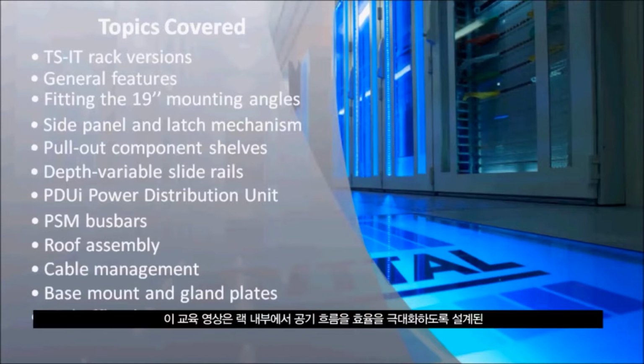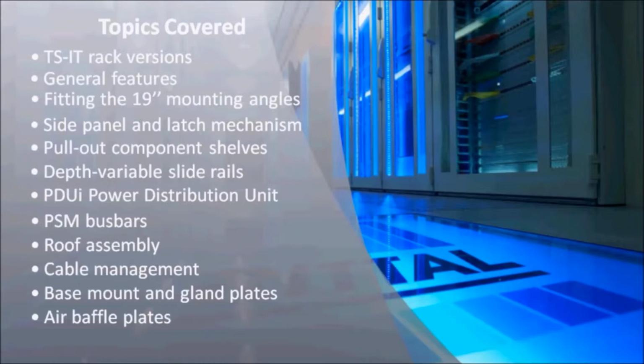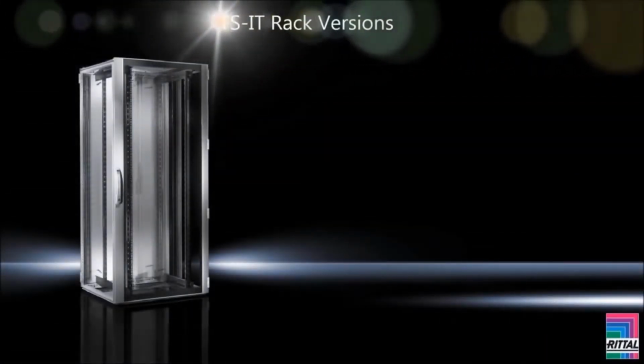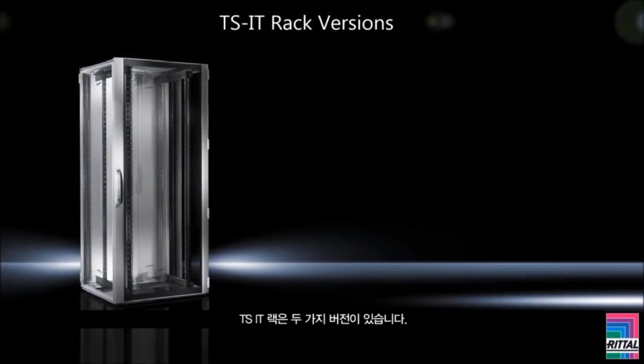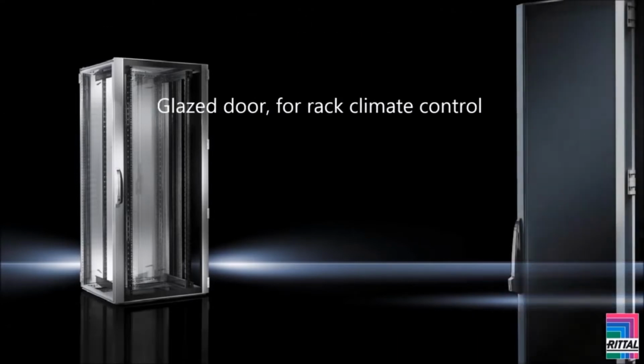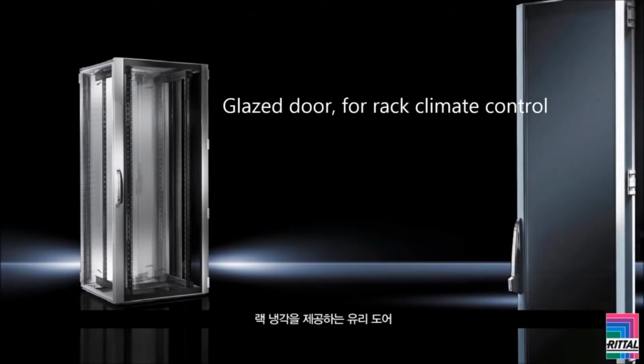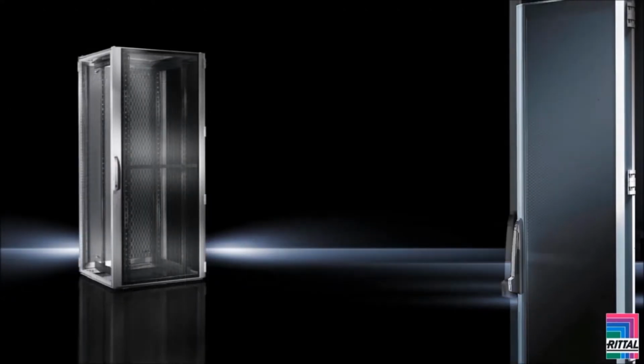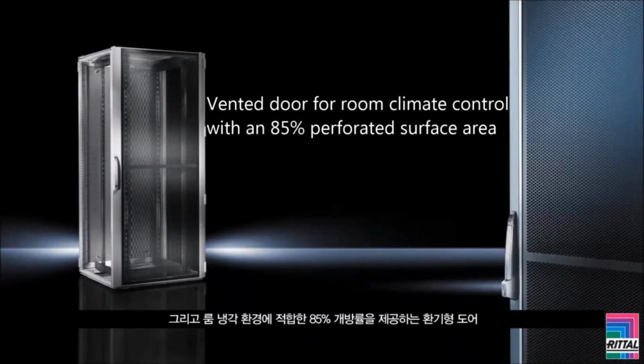And the training module will finish off with showing the air baffle plates, which are designed to maximize the airflow through the rack-mounted equipment. There are only two versions of the TSIT rack. Glazed door, for rack climate control. And vented door, for room climate control, with an 85% perforated surface area.